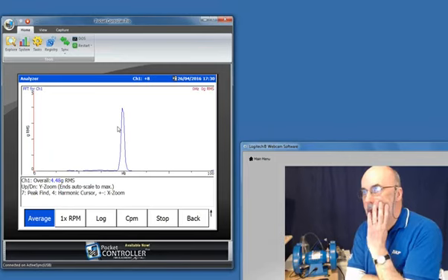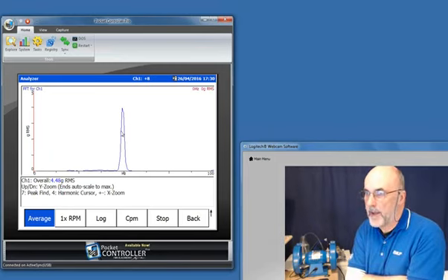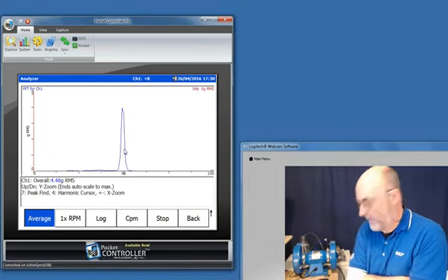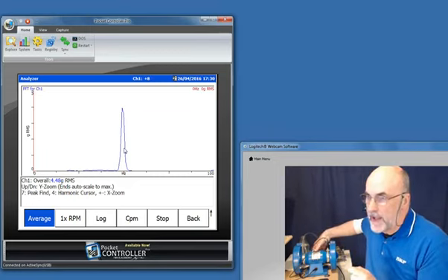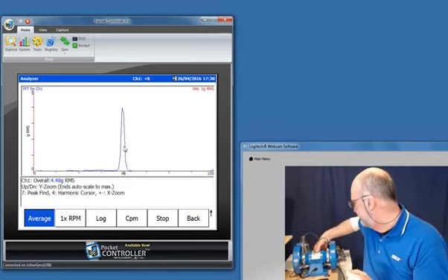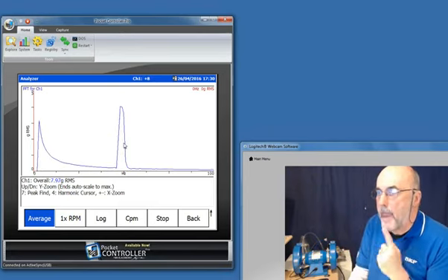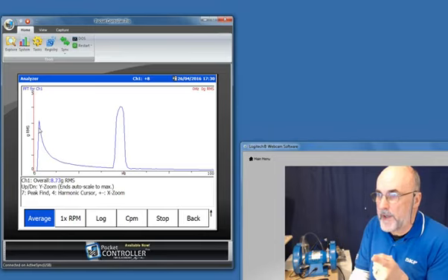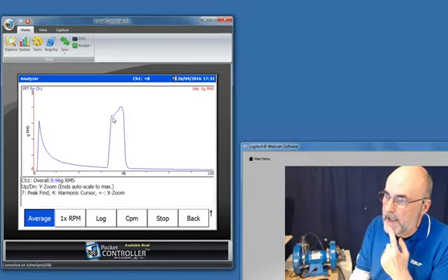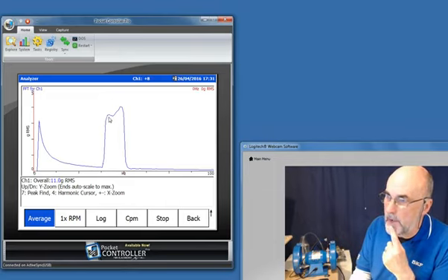Wonderful. So there's my peak. In America, you would get that at 60 hertz. Here it's running at 50. And we're going to track the machine now to make it slow down. There's a bit of a switching spike that came through on this demonstration. It didn't do this morning, but not to worry. So this peak here, this unbalance, is moving left as the machine gets slower and slower.